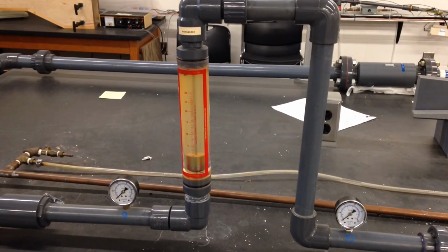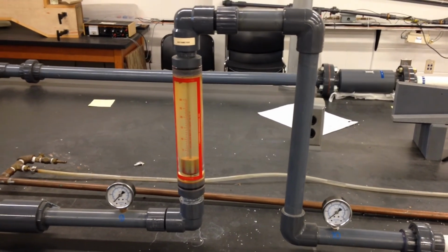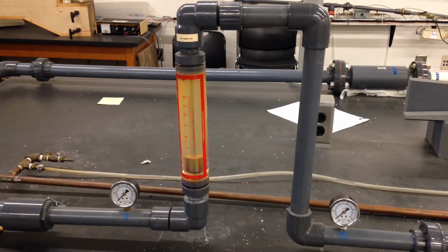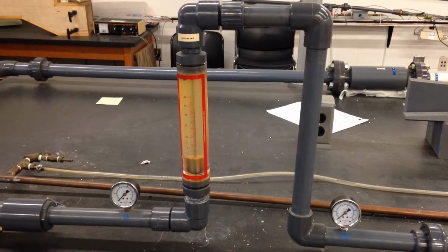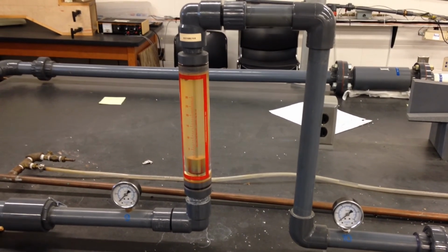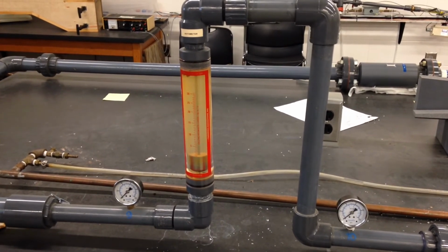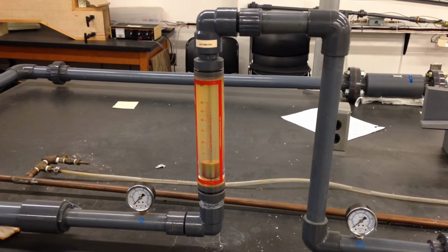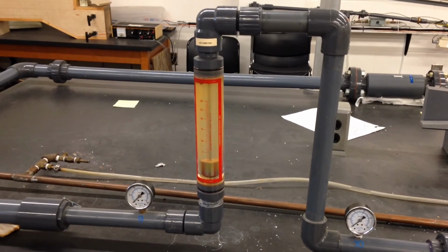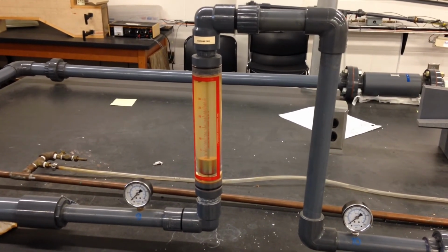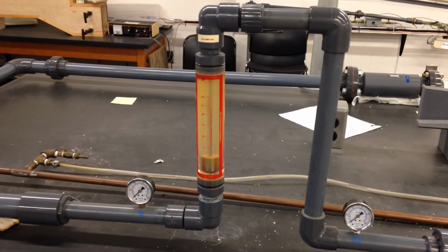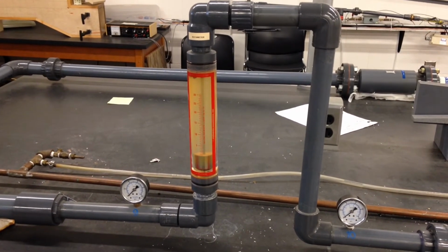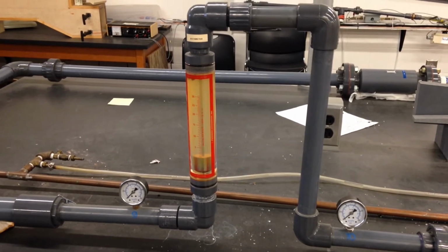What you'll do is a little different between it and the other flow meters. For the other flow meters, you have to go through the theory and compute their coefficient of discharge versus Reynolds number. With this, it's graduated in gallons per minute. All you do is plot this against that. The digital is your reference, and this is that. Obviously, if it were perfect, the 2 would be the same, and the line would be y equal to x. You will find there will be variations, and you'll have to plot and analyze that to see what type of differences there are and whether the rotometer is suitable for the application. It's very similar in concept to what we did with pressure gauge testing.